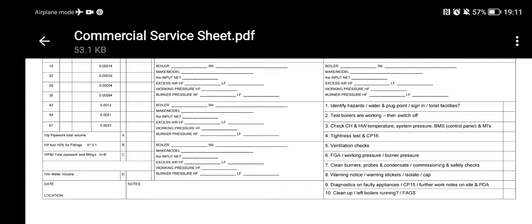Check central heating and hot water temperatures — check your gauges. You may walk in and see 65°C on the calorifiers. Whilst carrying out servicing, you don't want temperatures dropping to 30°C in a hotel, because there'll be unnecessary complaints. Also check BMS control panel errors, see if there are drawings or schematics, note which lights and relays are on. Are there manufacturer's instructions on site? If not, download some and have a quick 5–10 minute read of the manual — how to get the boiler in high and low, what the manufacturer states.